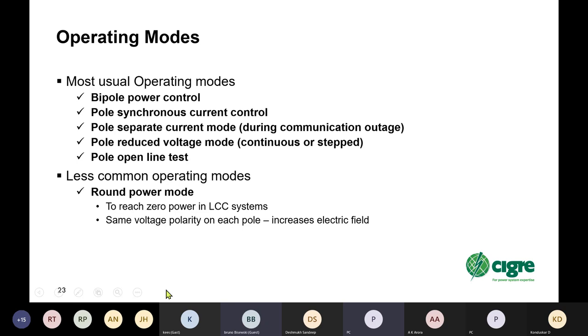And then for testing the line, there's an open line test mode that's possible, which should also be specified. Less common operating modes, especially with LCC, is a round power mode in which the power in the LCC system can be in opposite directions in each pole. That way you can adjust an LCC to reach zero power if necessary. Otherwise, the LCC has to operate at some minimum current, which implies a minimum power, especially if it's a large system and has a bipole and you're running both poles.